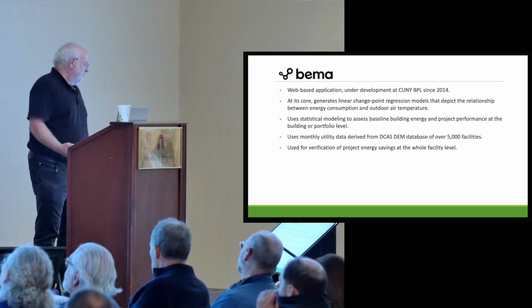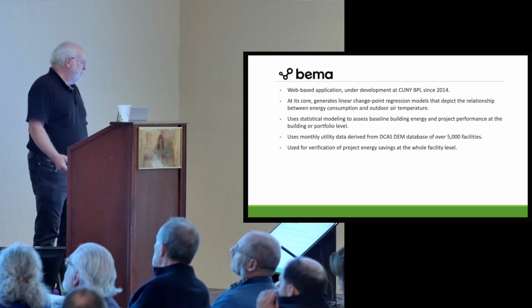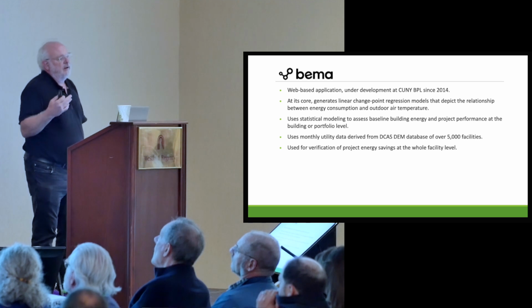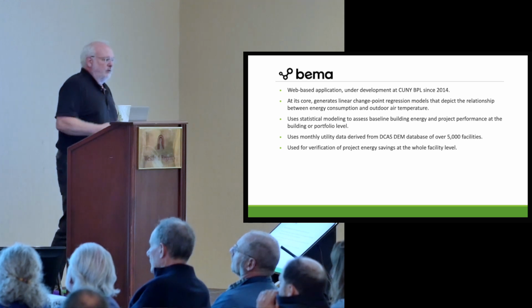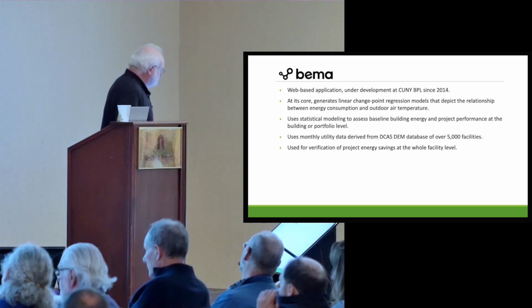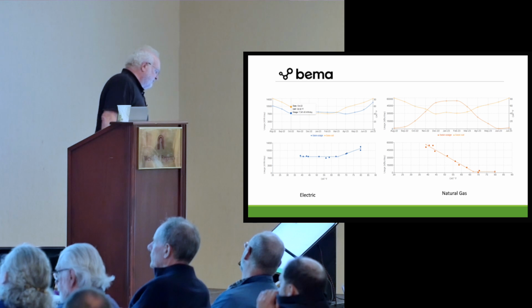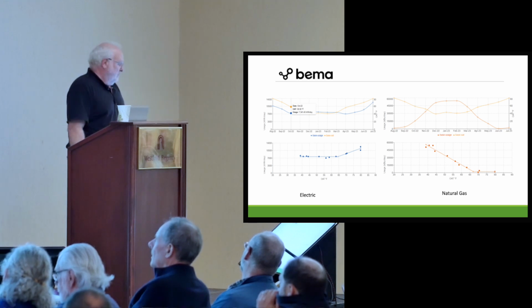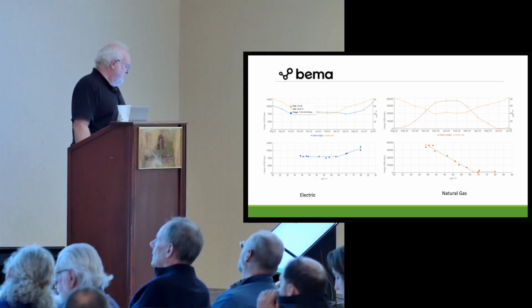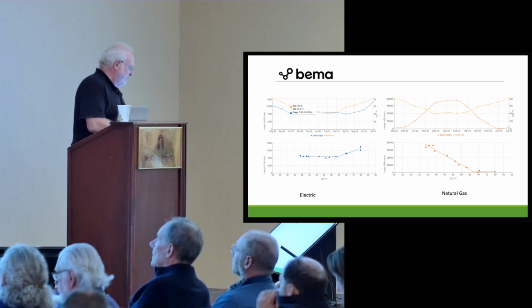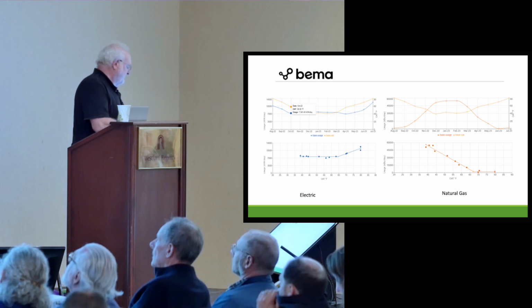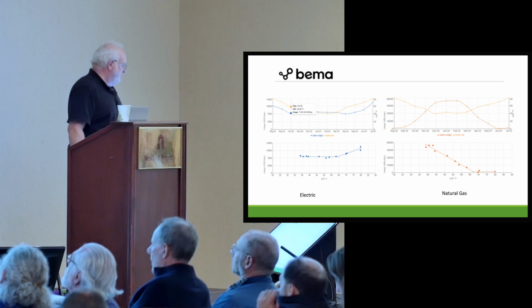It uses monthly utility data, and part of what we do with this is also use it as a measurement and verification tool for whole building analysis. These are some screenshots of it — a cooling model, electric versus natural gas. You've got a 68-degree change point there for heating, and about a 65-degree change point for cooling.